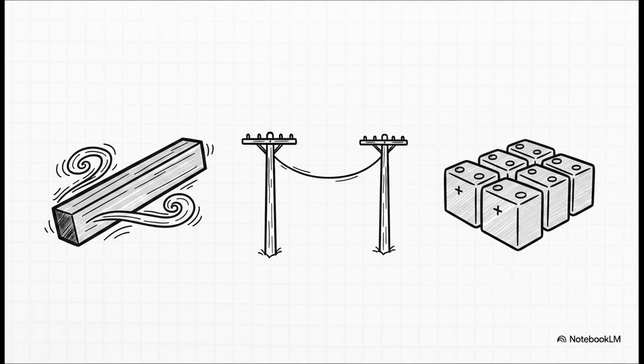In this module, you'll learn manual and software-based ways to calculate incredible forces. You've got to size your bus bars not just for the everyday current they carry, but to withstand the physical whip of a short circuit and extreme wind forces. We'll also run conductor sag and tension analysis for extreme weather conditions.